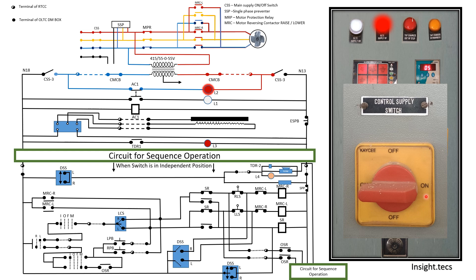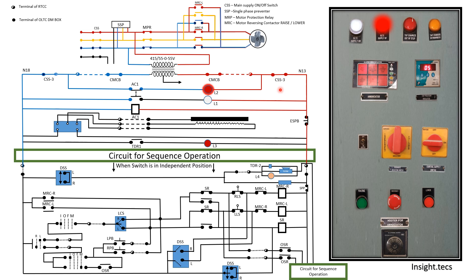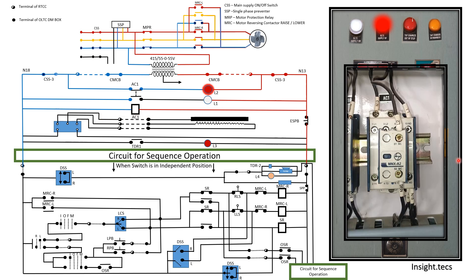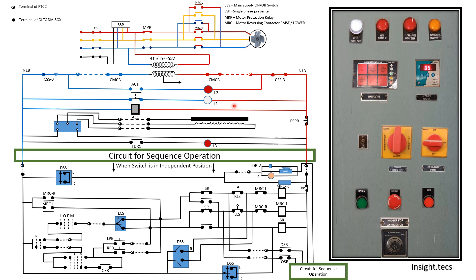The CSS3 switch is located on the RTCC panel itself. Once it is turned on and power supply reaches the RTCC panel, the AC1 contactor will be operated and gets energized. Because of that, this contact will be closed, the NC contact will open, and L2 will stop glowing. Instead, L1 LED will glow, indicating that OLTC supply is on. This is the working of the AC1 contactor.